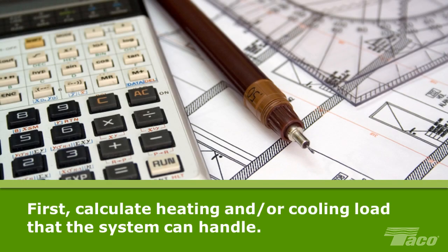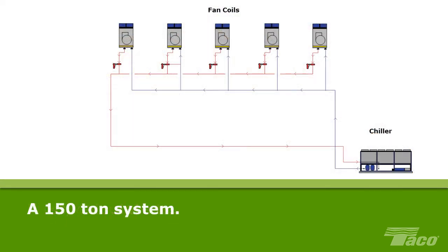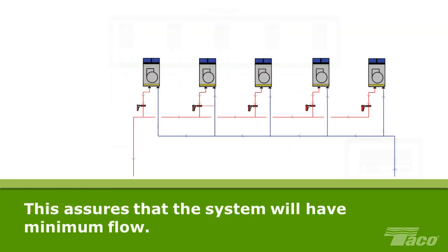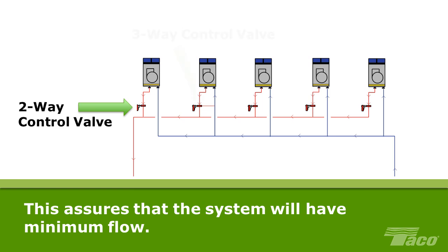When an engineer designs a hydronic system, he or she begins by calculating the heating and/or the cooling load that the system will be required to handle. Here's a simple example system. Based on the load, the engineer has determined that this will be a 150-ton system consisting of a chiller and 5 fan coils. 4 of the fan coils are fitted with a 2-way control valve. The 5th has a 3-way control valve to assure that the system will have minimum flow.